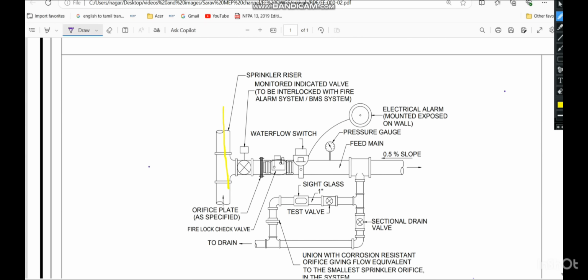So we have the riser here. We are taking the zone control assembly here. The first one should be the isolation valve to isolate the full system in this side area. So first, after this should be the supervisory valve, supervisory isolation valve. Mostly it will be butterfly valve we provide here. After that, we have the water flow switch at this point. Then we have the pressure gauge. Then this system line will go to the sprinkler system. And here we have taken the branch line.